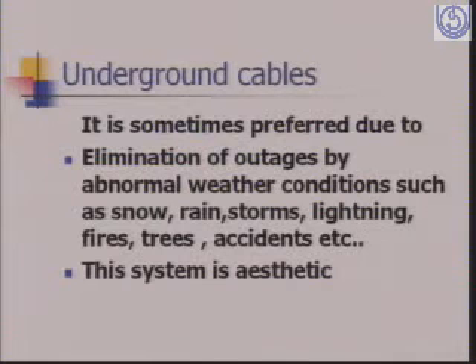We'll go to the underground cables. These are also being used at 11 kV and LT, and sometimes at 33 kV. They are very expensive as compared to the overhead lines, but still they are being used. They are sometimes preferred to eliminate outages caused by abnormal weather conditions such as snow, rainstorms, lightning, fires, trees, accidents, etc. So if we want to increase the reliability, we use underground cables.